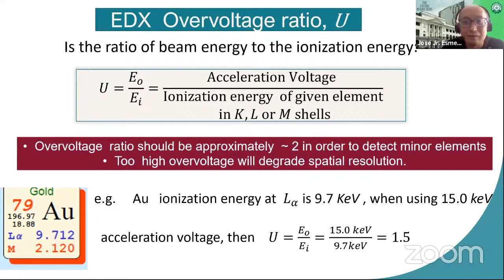So what does this overvoltage affect? You can see from here, if I use only 3 kV acceleration voltage, at a certain point I see fewer elements. It's hard to identify what they are. In the basic periodic table, you won't see anything at all. If I increase the acceleration voltage to 15 kV on the same material, you can see a lot of elements sprouting out from the spectrum, so you can identify a lot of elements. It can even see the sputter coating on that material, the platinum. So that's the difference between the two acceleration voltages. That's what the overvoltage ratio does.